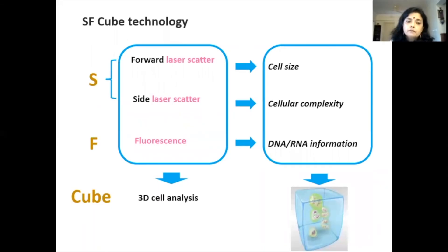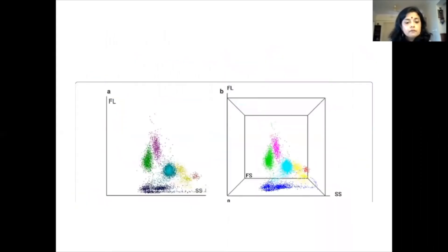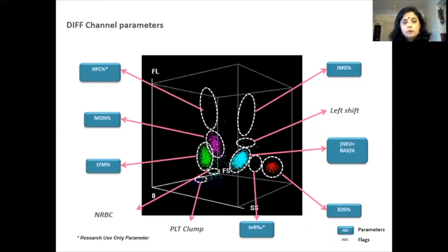The SF cube technology — where S is for scatter and F is for fluorescence — is available in many analyzers. What makes it unique is the 3D cell analysis, which gives an idea of cell size, cellular complexity, and cellular composition including DNA and RNA information. Looking at the forward scatter and side scatter histogram available in most machines, what is unique here is a 3D interpretation of the cells. In the DIFF channel, the parameters break up accordingly.